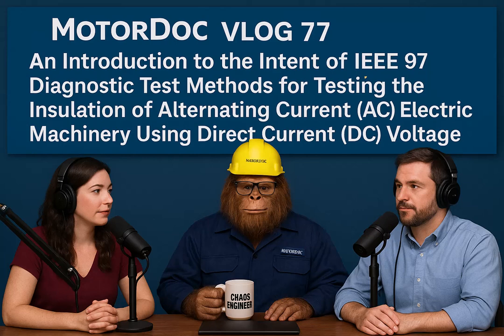The guide really focuses on 3 advanced DC tests that give you this extra layer of diagnostic insight. There's the DC ramp test, or DCR. Yeah, got it. Then the polarization and depolarization currents test, PDC. PDC. And finally, the insulation resistance profile test, or IRP. DCR, PDC, and IRP. And taken together, what sorts of insulation problems can these tests help you find?